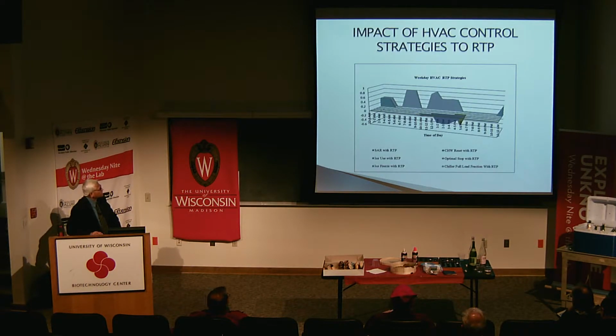Now here is the same thing as I explained before. The upper portion is chiller load. This is ice being made. Here is the floating control advantage. Chiller is shut. Then the chiller is run to meet the load. Here, I'm sorry, here is optimal start. Here is the floating control. Here you are melting ice. That's why the peak has dropped from here to here.